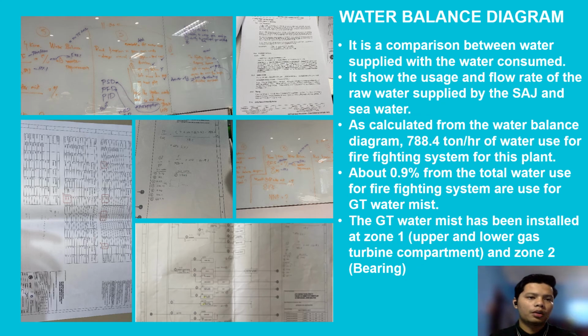Water balance diagram. The water balance diagram compares the total water supply to the site, the actual water consumed within the site, and the total water leaving the site. This will help to identify areas of significant water usage and problem areas, including leaks and uncontrolled losses. It will show the flow rate in units of tons per hour, and the water usage in each section.